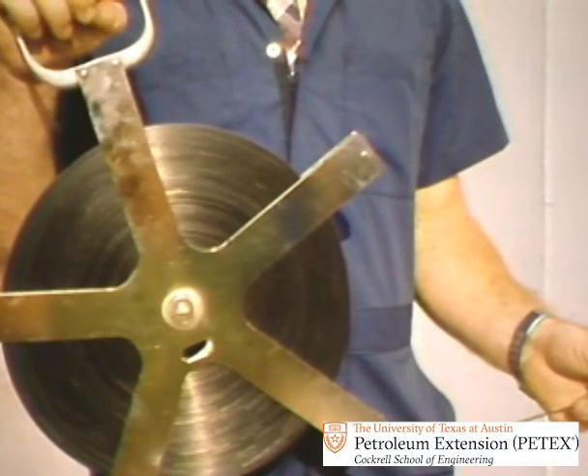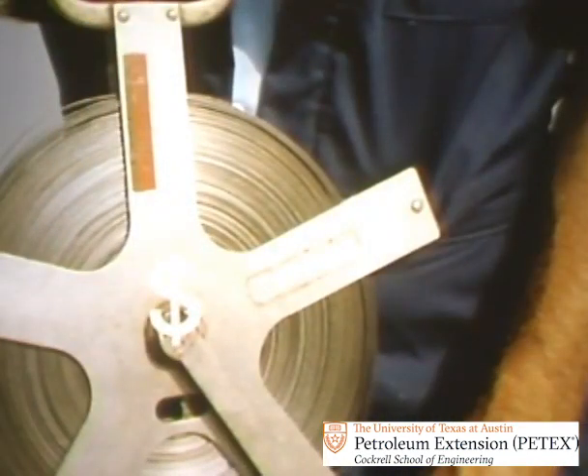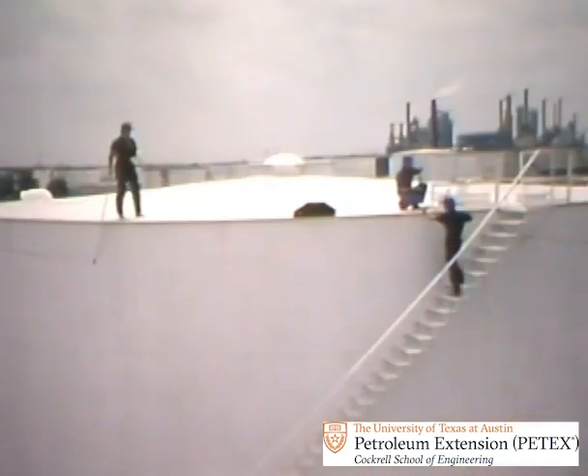A working tape like this one is not calibrated by the National Bureau of Standards. Instead, the strapping crew has to calibrate the working tape to the standard tape. Now, why not use the standard tape for all measurements? Well, the answer is that if a standard tape is damaged, its accuracy is voided. Plus, you have the expense of replacement, not to mention the time lost while you're waiting for a new tape to arrive. And it's fairly easy to damage a tape while strapping.